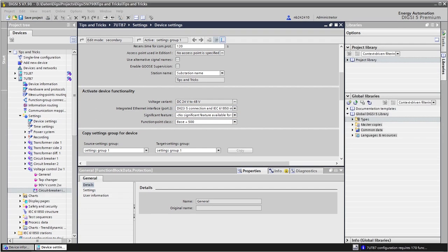The communication between the Siprotec devices is handled via so-called proxies. Every device needs a proxy for every other device it should communicate with. In our example with three transformers in total, every device communicates with two other devices. So in every device we need to configure two proxies.